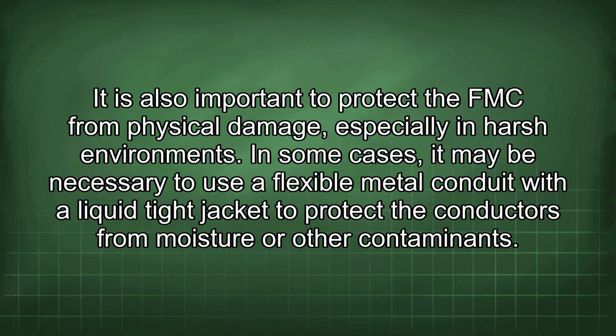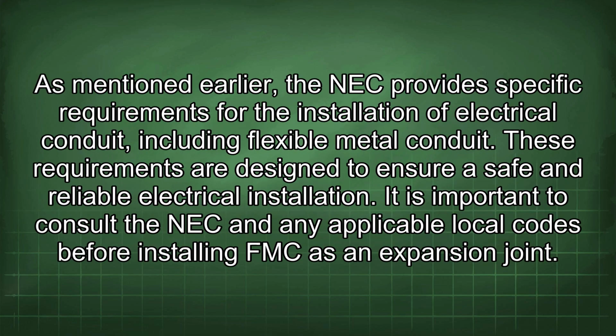It is also important to protect the FMC from physical damage, especially in harsh environments. In some cases, it may be necessary to use a flexible metal conduit with a liquid-tight jacket to protect the conductors from moisture or other contaminants. As mentioned earlier, the NEC provides specific requirements for the installation of electrical conduit, including flexible metal conduit. These requirements are designed to ensure a safe and reliable electrical installation. It is important to consult the NEC and any applicable local codes before installing FMC as an expansion joint.